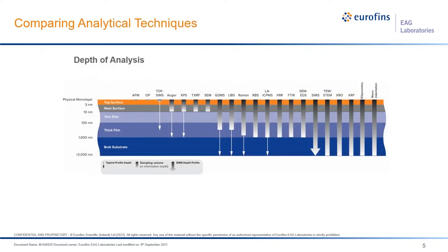X and Y sizing isn't the only dimension to consider in surface analysis. We can compare techniques by their depth of penetration. On the left are the very surface-sensitive techniques — AFM, time-of-flight SIMS, Auger, and XPS — which look at the first few atomic layers down to about 10 nanometers. Raman, RBS, and XRR look deeper still, and almost-bulk techniques include XRD, XRF, TEM cross-section, and SIMS depth profiles. SEM-EDX sits at the near surface down to about 1,000 nanometers (one micron), but that depth is variable and we can use that variability to our advantage.